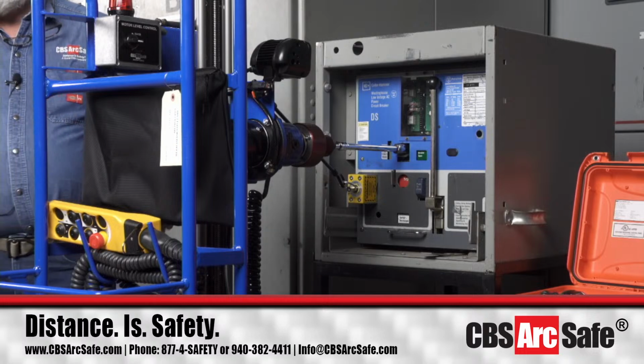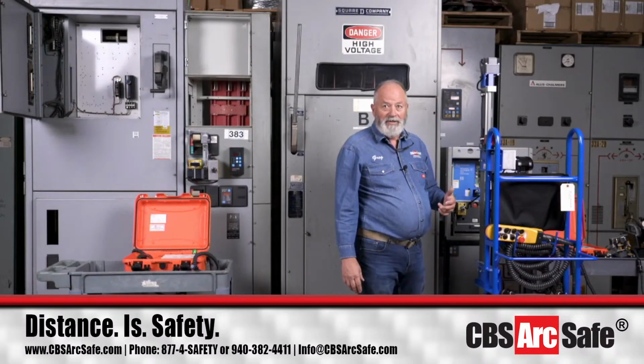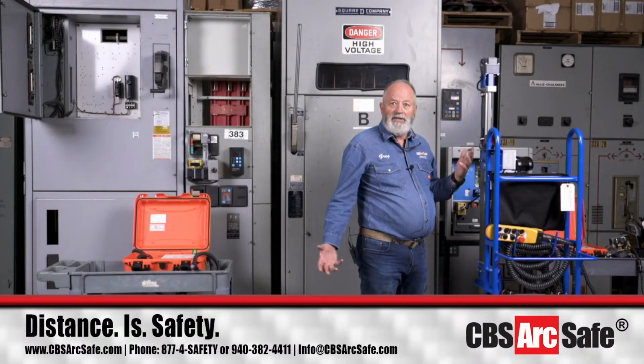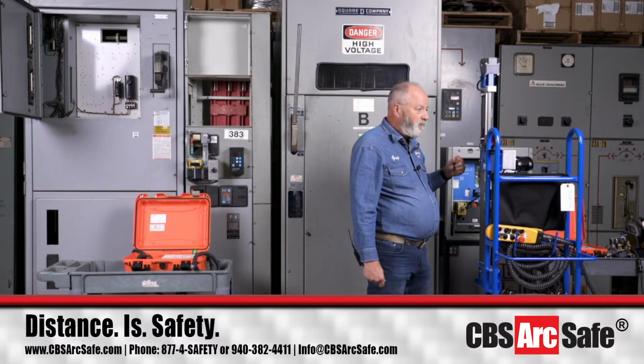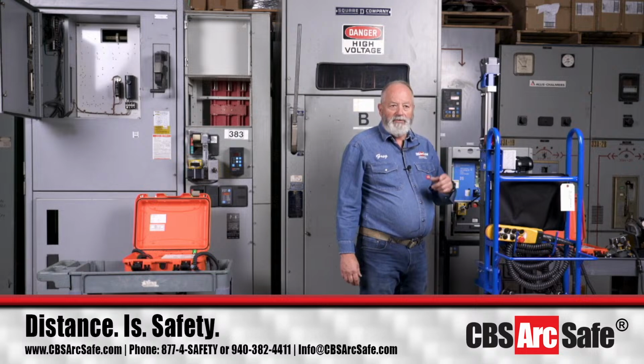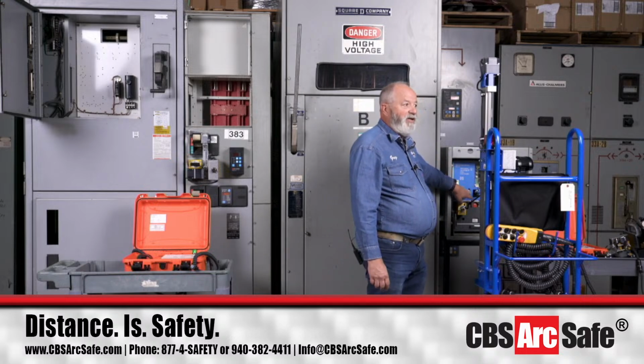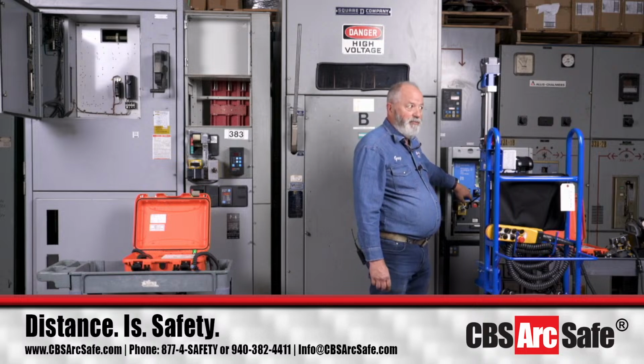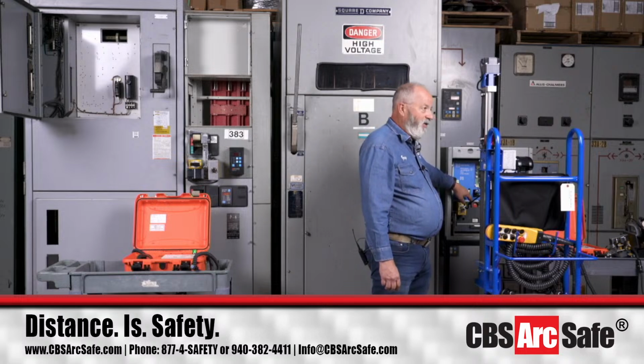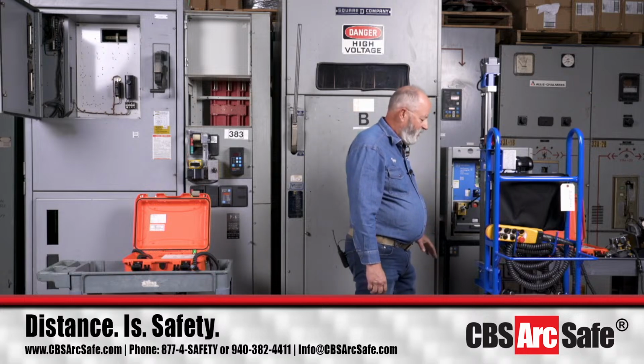How do you know? I said, you see that black mark? Yeah, that's where I made the mark to know where it was. And they opened the next cubicle and they're like, it is in all the way. So unlike the newer breakers like a Magnum DS where you got a red, yellow, and green indicator at the bottom, this one's not quite as accurate. It's just based upon the guy who put this little aluminum tab in here and where it got bent the day he installed it. So just to make note of that.